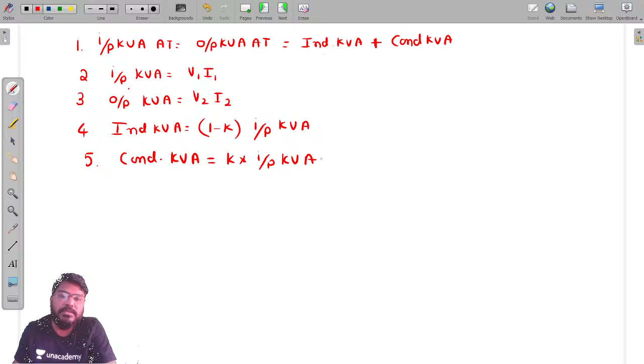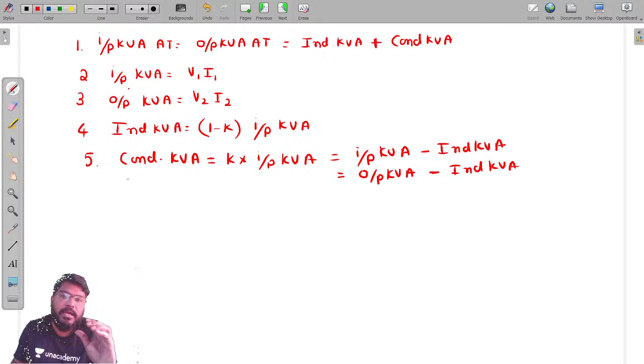In an auto transformer there are two windings - some number of turns are electrically connected, some number of turns are electrically isolated. If power is transferred from the electrically connected part of the winding from source to load, that power is called conduction power. If power is transferred from the electrically isolated part of the winding from source to load, that power is known as induction power.